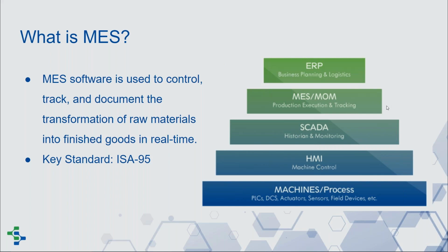As we go up to supervisory control and data acquisition, or SCADA, we're now aggregating data from multiple equipment, multiple processes. And so our time scale increases. Rule of thumb is around a second. And our distance from the physical process has increased, right? We're not immediately immersed in it like the control layer, or a step away like an HMI. Now we're looking at maybe the whole plant. And the rule sets and the data become more complex. So now we're talking about aggregating historian values and doing some calculations, doing alarming and some of those monitoring features, right? So when do we escalate this alarm? That's a more complex rule set to more complex data than we necessarily saw in the control or HMI layers.